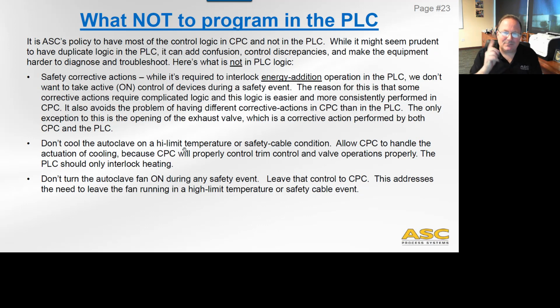So here's what will not be in the PLC logic now. First is the safety corrective actions. While it's required to interlock energy addition operations in the PLC, we don't want to take active on-off control of devices during the safety event. So what that means is it's okay to block signals going out to valves and this type of thing, but we're not going to be turning things on like cooling pumps and cooling valves and that type of thing.